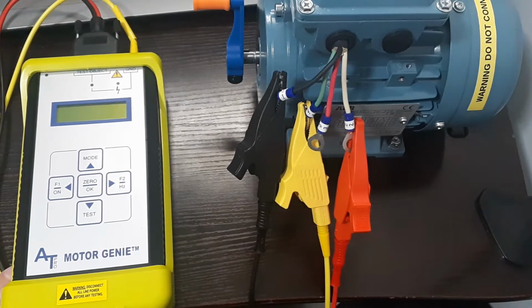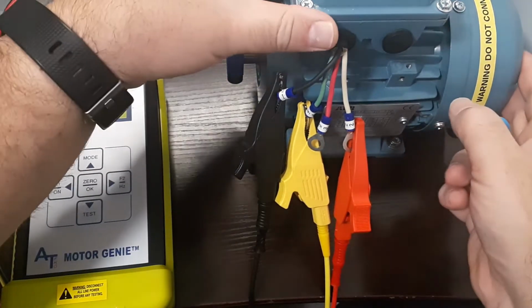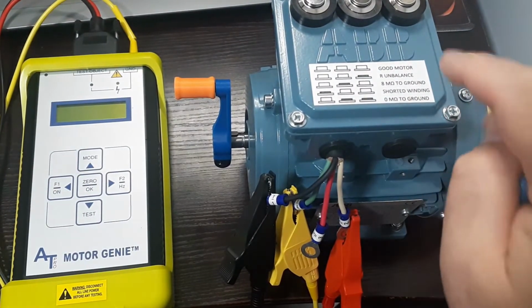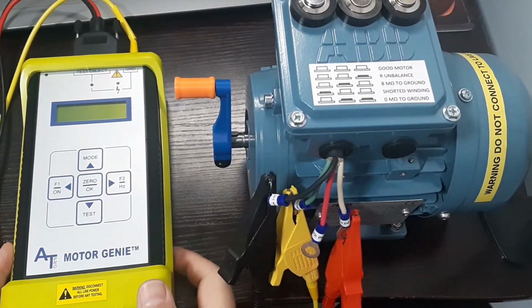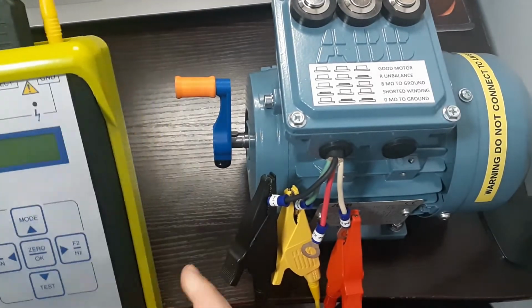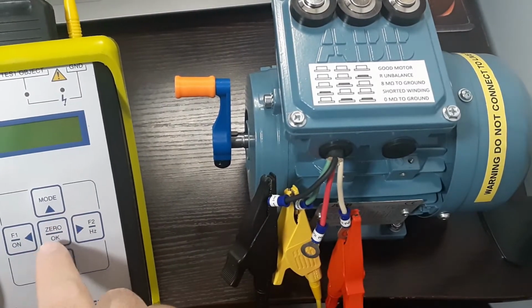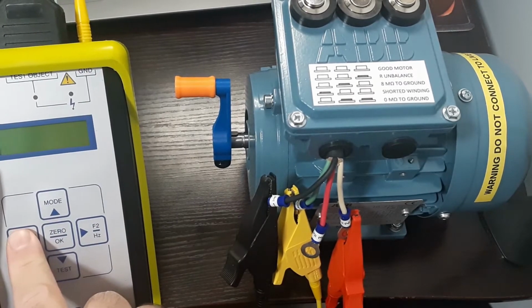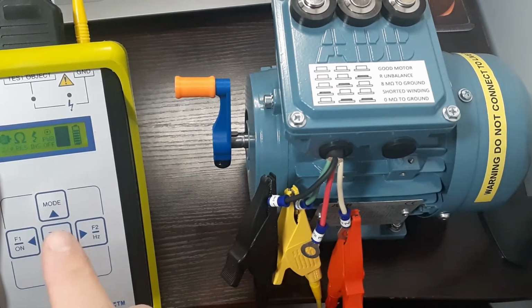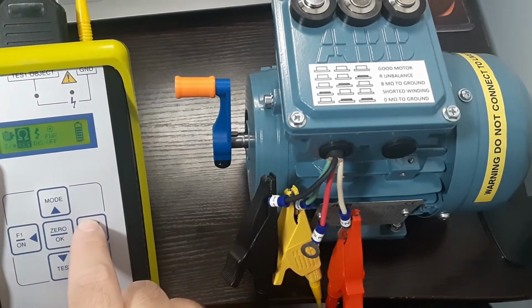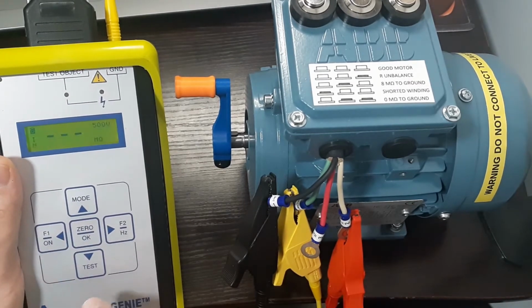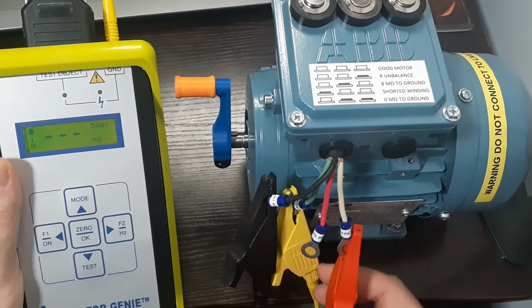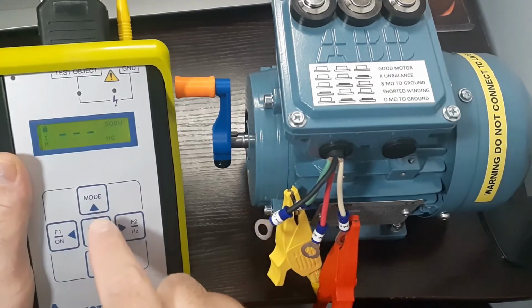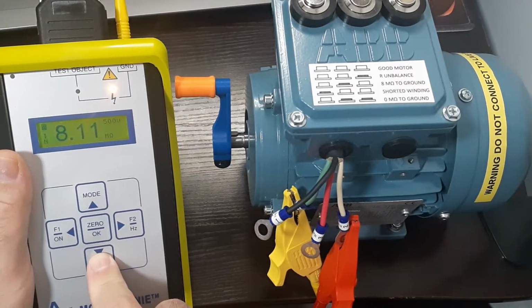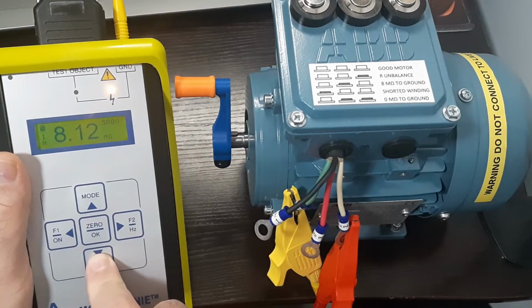Okay, so we're back. We're gonna demonstrate a couple faults with the Motor Genie in this video. So first thing I'm going to do is we're going to do a ground fault. Let's go 8 mega ohm to ground. So this is what a Megger would pick up. So just to demonstrate that it can do it, we'll go to the insulation test. And I'm just going to take off black. Yep, we have 8 mega ohms to ground.